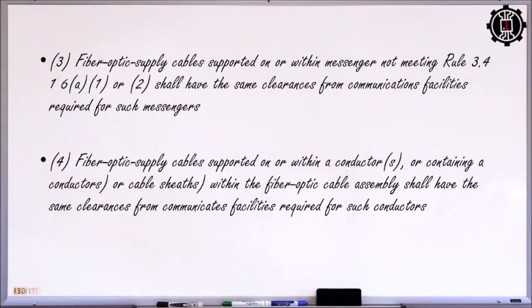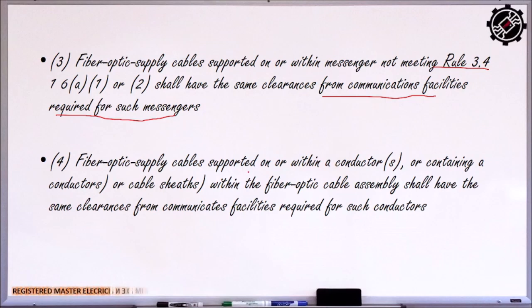Then the fiber optic supply cable supported or within the messenger not meeting this rule shall have the same clearance for communication facilities required for such messengers. So ito na yung pinaka-kanya, 4.8 meters at 2.7. So fiber optic supply cable supported or within a conductor or containing a conductor or cable sheaths within the fiber optic assembly shall have same clearance from communication facilities required for such conductor. So, pareho lang tong dalawa na clearance.